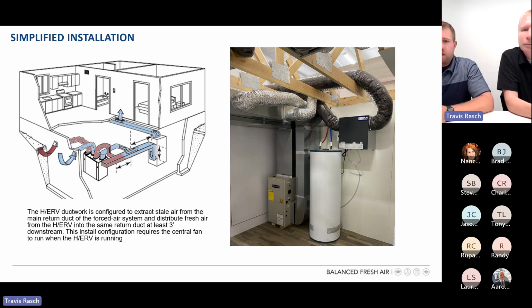There's an alternative: instead of putting the fresh air into the return side, you can put it into the supply side. There are other things to be mindful of when you do that. You should still have interaction with the air handler, because during a cooling heavy time of year, the air conditioning ductwork, particularly sheet metal, could be very cold. Even though the HRV or ERV is tempering that air well, we could still be pushing warmer air onto a very cold surface, raising concerns about condensation on that ductwork material.